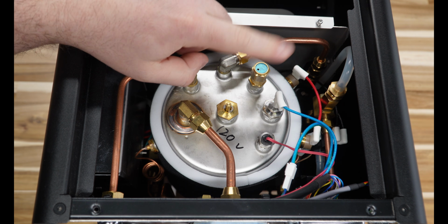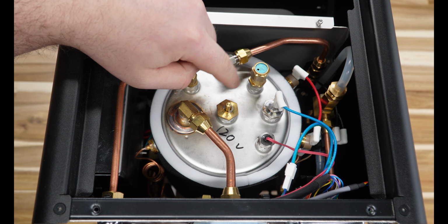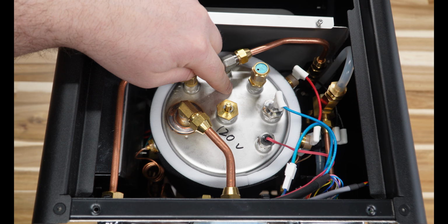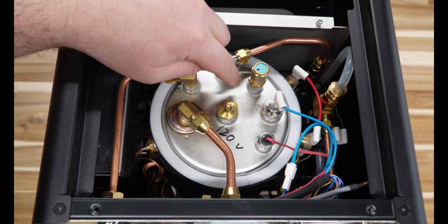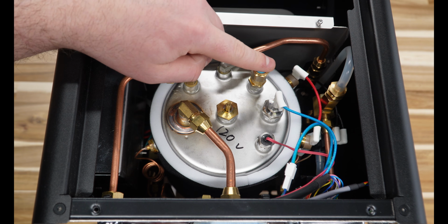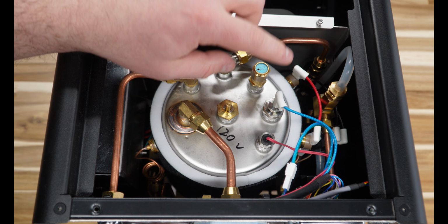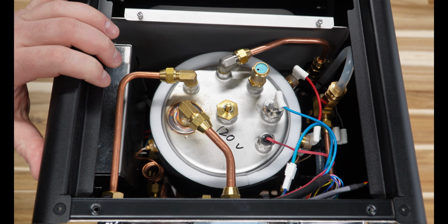The next thing we have here is our overpressure valve for protection on the boiler. If for whatever reason this thing had an issue where the element stayed on, this is what would release the pressure. Really nice Italian-made component. A lot of times these are pretty junky on a lot of machines that you see out there.